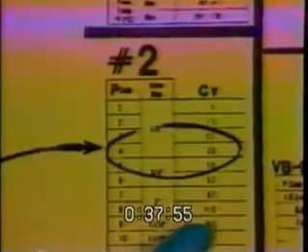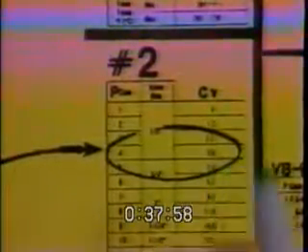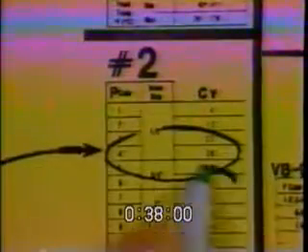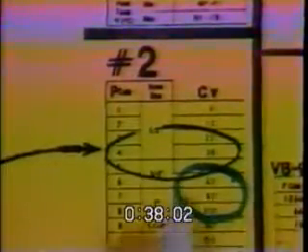If you go down here to the number 2, we're going to look for our CV. This is our calculated CV. We're looking for something as close to 8 as we can get. In our example, 8 is right here. So we want a CV, or a port code rather, of 7. It has 8.2. That means a port code of 7. So I put a -7.